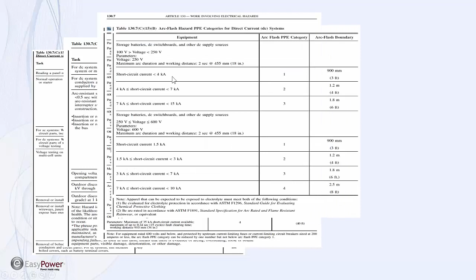The same thing applies here, and notice that at no point are they talking about incident energy—that's probably the first big clue. This takes us down to a description of what each category requires, between Category 1 and Category 3. Looking forward to answering the original question, we can see a number of things have changed. It's not quite as simple as what happened to Category 0. For instance, there is no HRC category to start with, and in fact there's no HRC table. This is a PPE category.